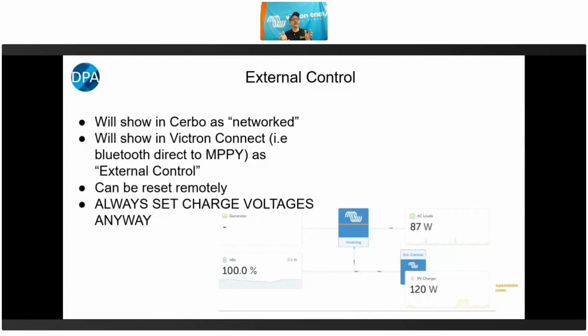And so it's taking the control away from the internal set points that we've just done on the charger, and it is telling it what charge voltage to take it up to and what its maximum current is and things like that. So when you connect to it, the Cerbo is automatically going to detect this BMS connected battery, say Pylontech, and it's going to automatically put the MPPT into networked or external control mode.